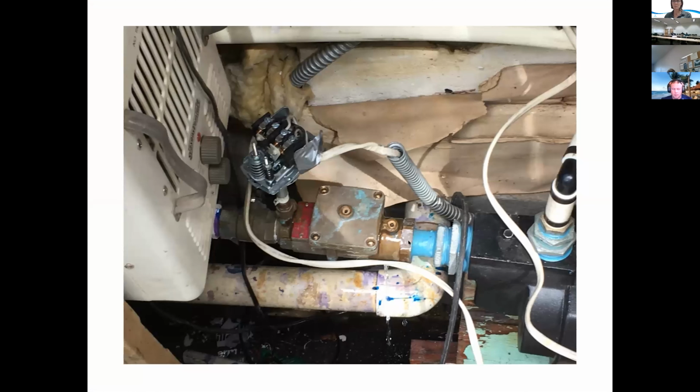This is another one of my favorite pictures, just because I love duct tape. Can you guys see what's going on here? So there's your double check valve assembly going directly into a pump. You've got your number 1 test cock is now the pressure switch. You got a heater here because it obviously freezes. Covers are optional, I guess, for the pressure switch. The other test cocks have been broken off. I love this picture, man. This is just something I would do.